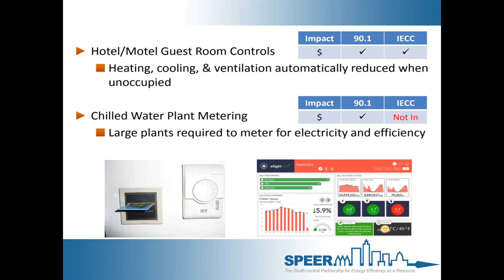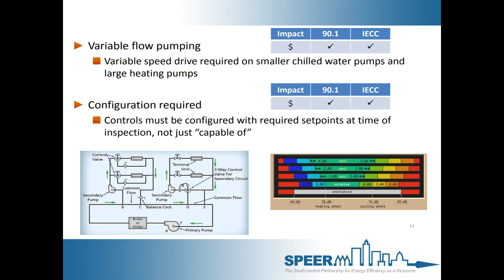Some variable flow pumping - the variable speed drive is required on some of that stuff, depending on size. In the 2015 IECC, the controls just had to be capable of set points. Now at CO inspection, those controls are required to be configured rather than just capable of being configured. A slight change there - typically if you're enforcing the commissioning process, the commissioning provider is the one who catches this kind of stuff. So that's another reason to go ahead and enforce the commissioning requirements in the code.